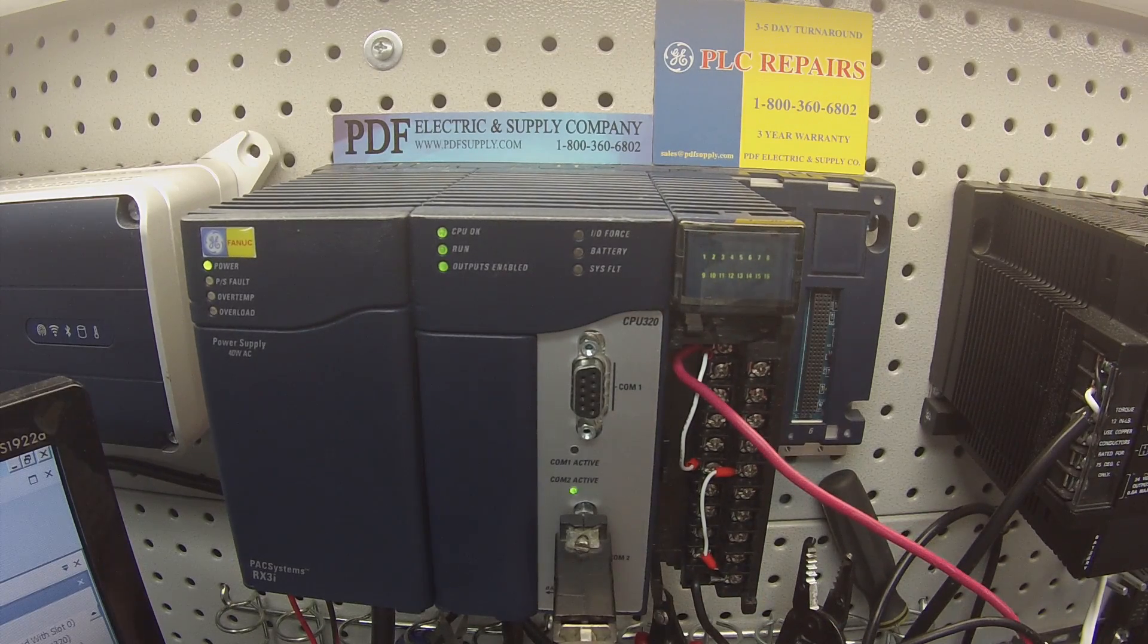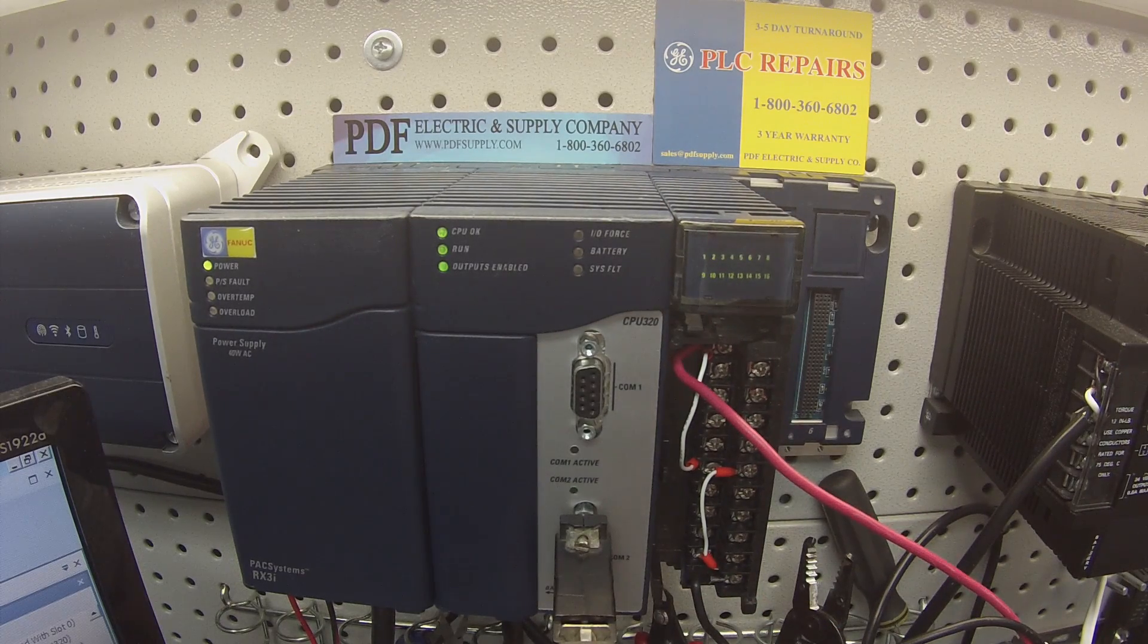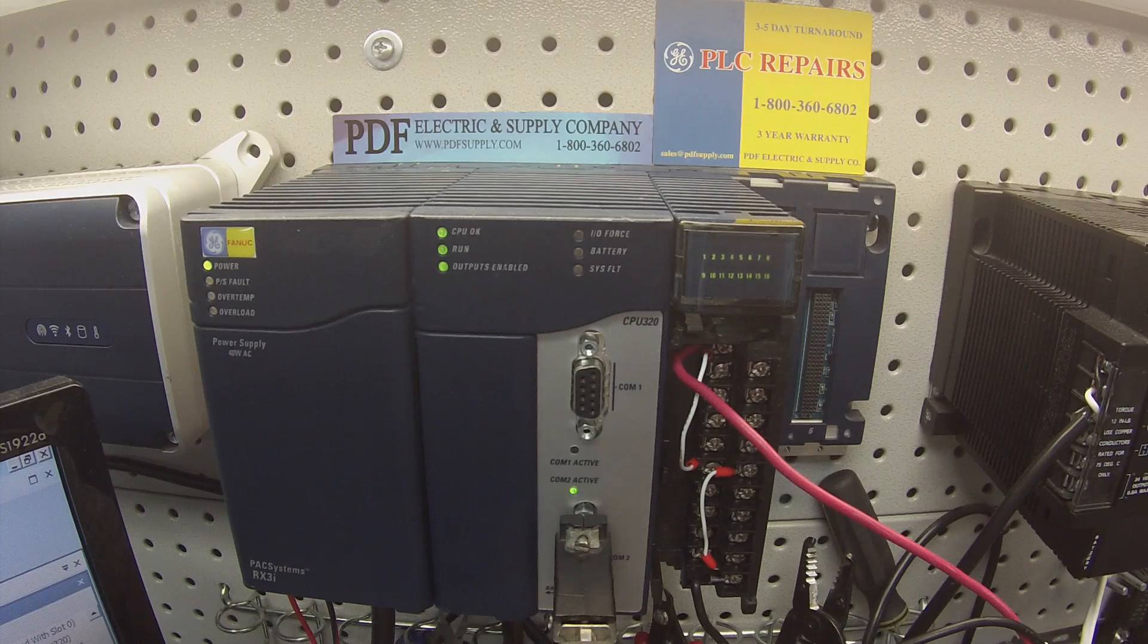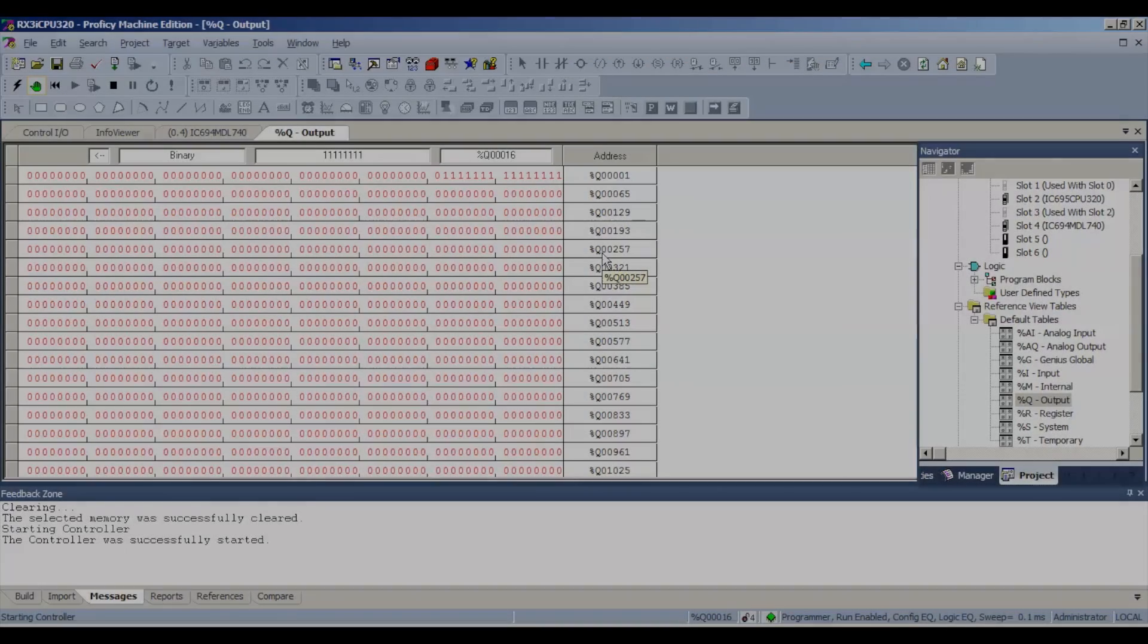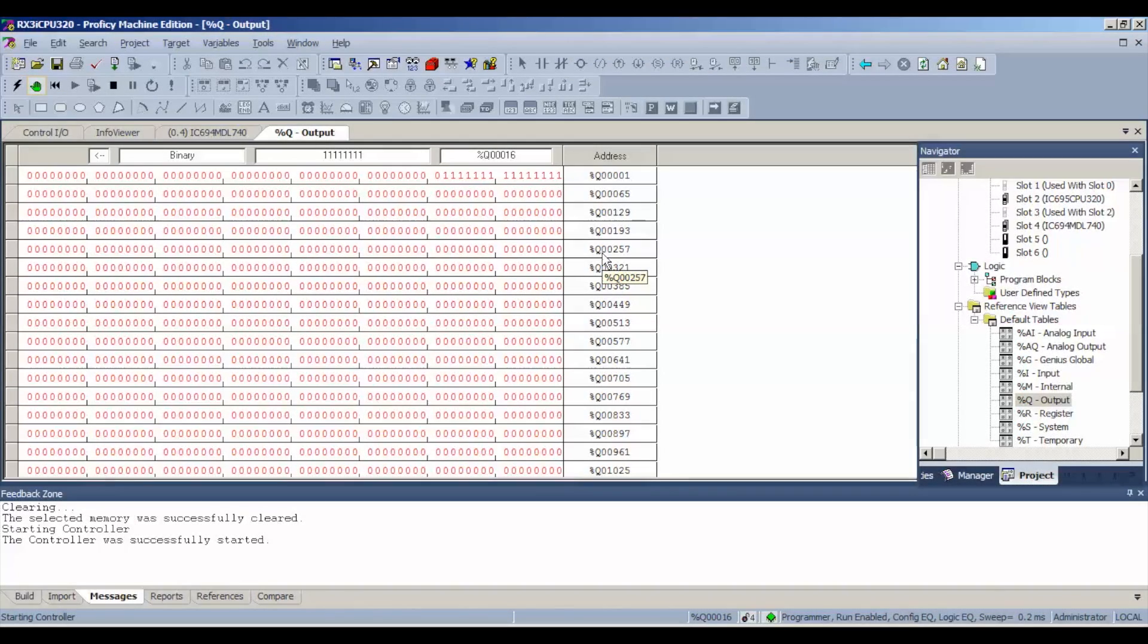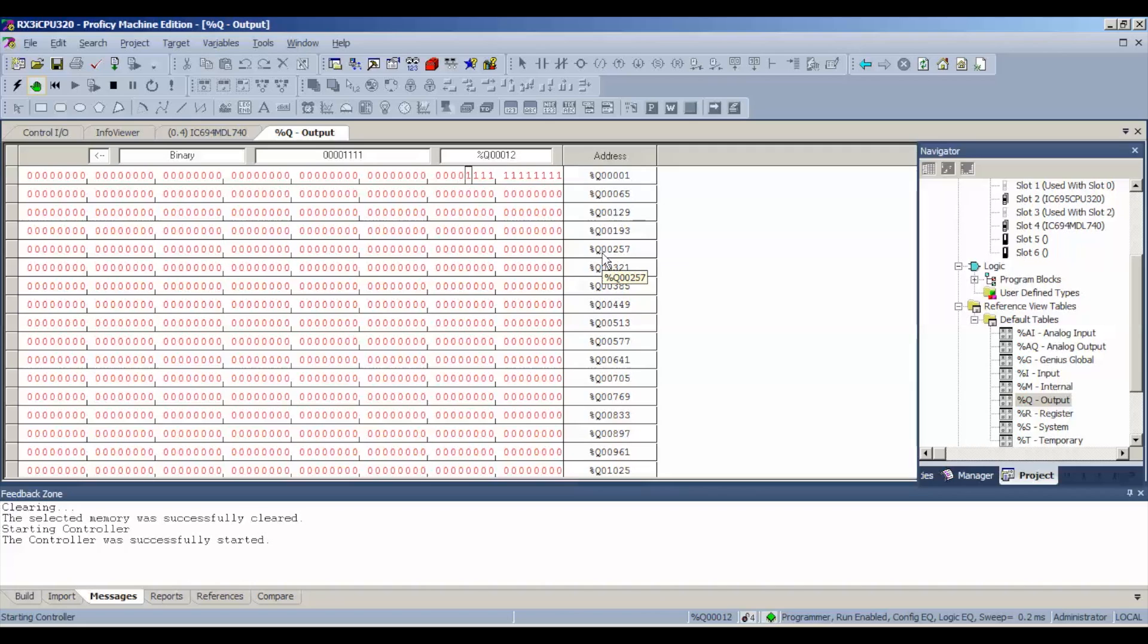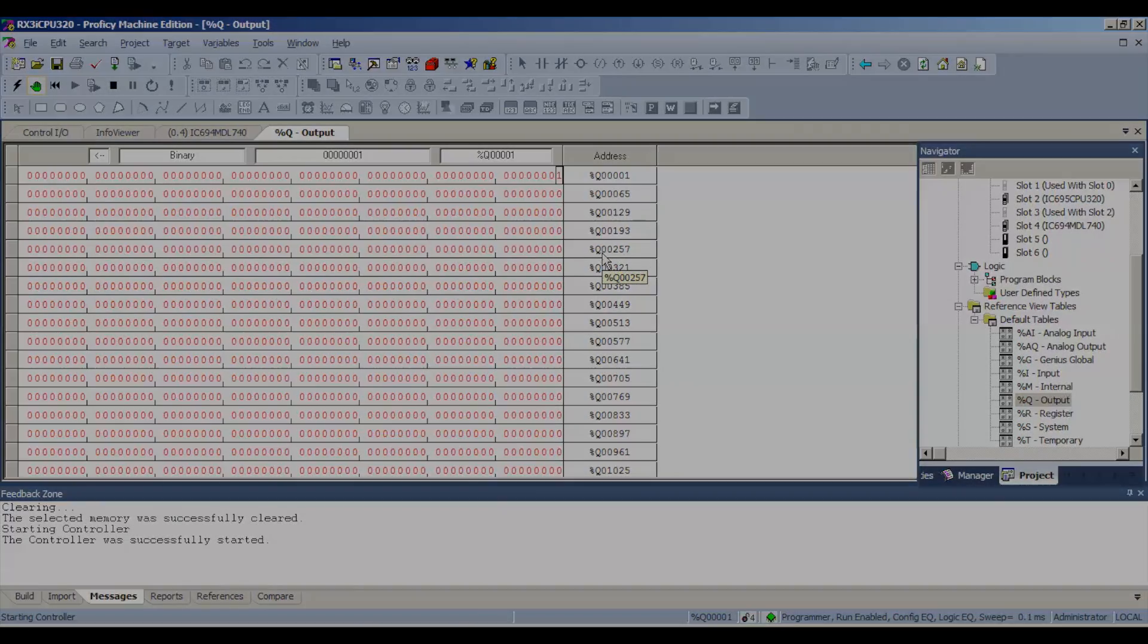Next thing that I want to do to make this test thorough is I'm going to put a zero. We know that the outputs are enabled and they're working but we also need to make sure that they shut off. This is where you're going to find most failures. One is that if you toggle the bit on and the LED on the user reference on the screen of the actual module itself is not turned on and there's no power to that particular circuit or channel, then that means that that's not working obviously.